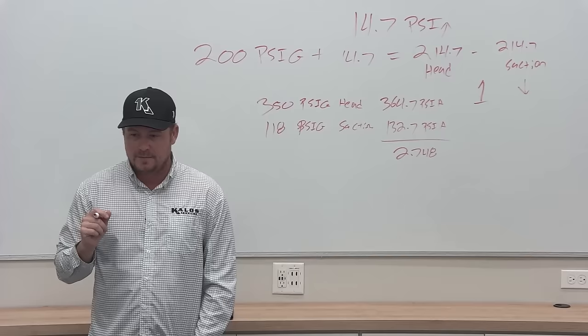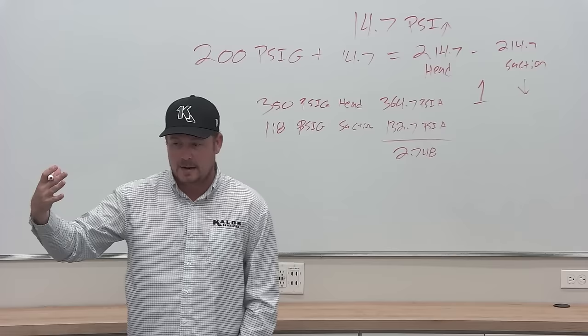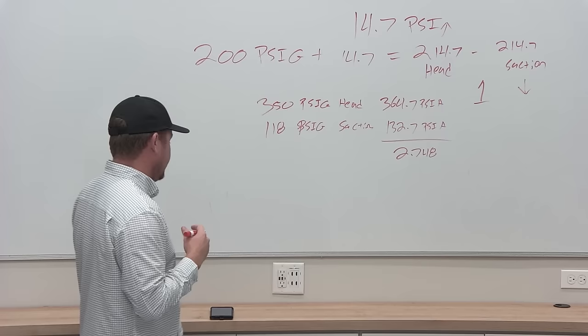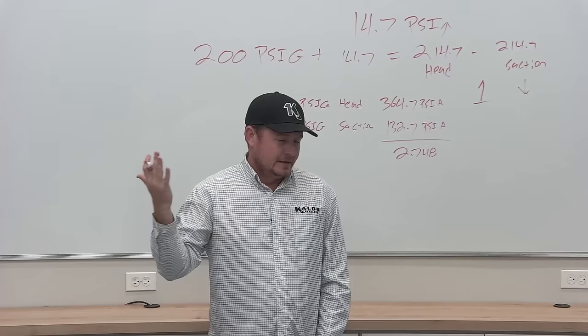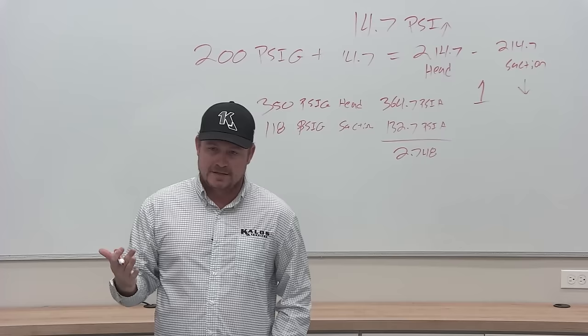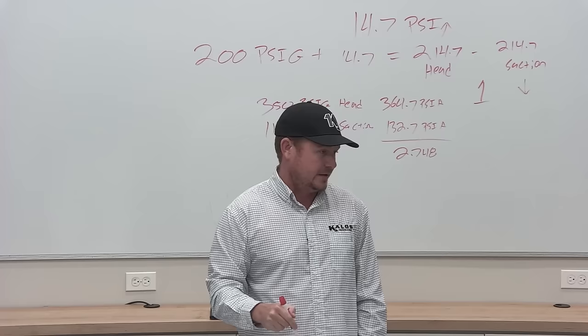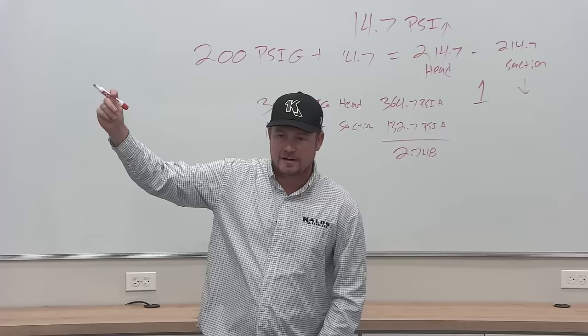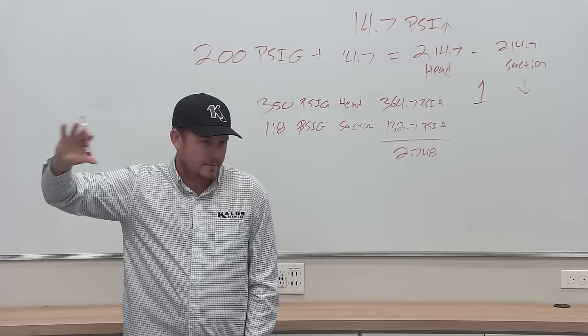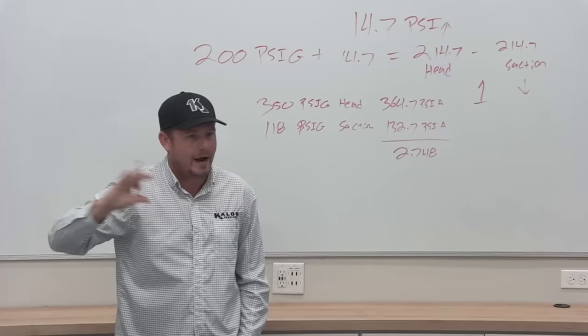You'll actually see lower compression ratios on higher efficiency systems — the bigger the condenser coil and the bigger the evaporator, the more you'll see that number drop. On refrigeration systems, you're still tied to the outdoor temperature for head pressure because you're rejecting heat outside. In some self-contained cases, head pressure is lower because the store is cooler. But if you're rejecting heat outside, your condensing saturation temperature is going to be about the same as it is for air conditioning.